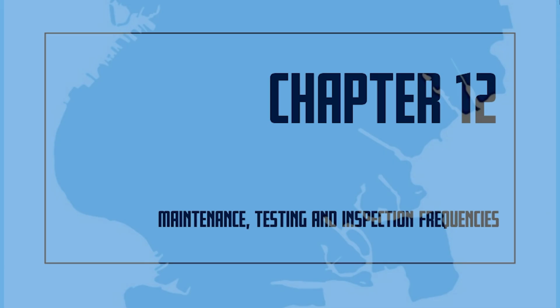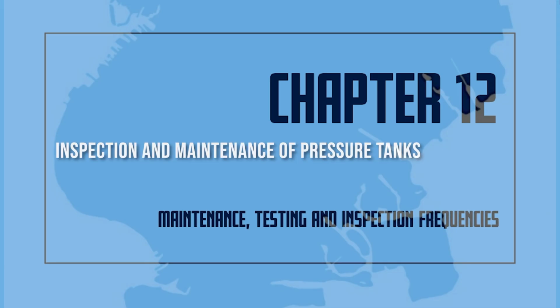12. Maintenance, testing, and inspection frequencies. Inspection and maintenance of pressure tanks. The water level and air pressure in pressure tanks shall be inspected monthly and maintained in accordance with the National Fire Protection Association, number 25, 2002 edition. The water level and air pressure must provide an adequate water supply to the sprinkler system. The capacity of the compressor shall be sufficient to build up the tank pressure to 75 psi within 3 hours or less.